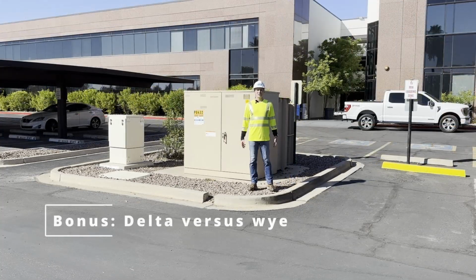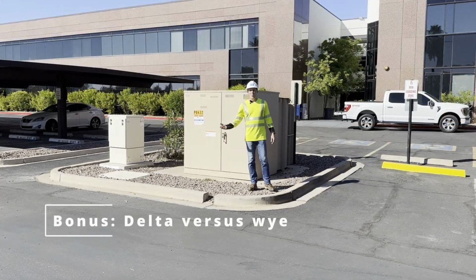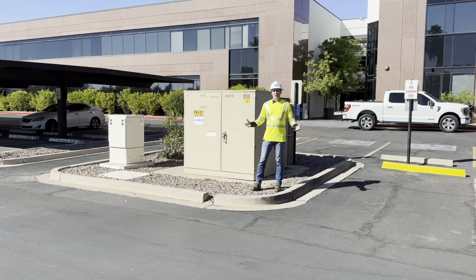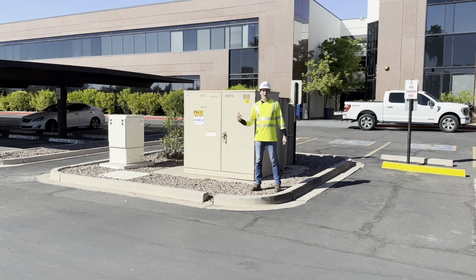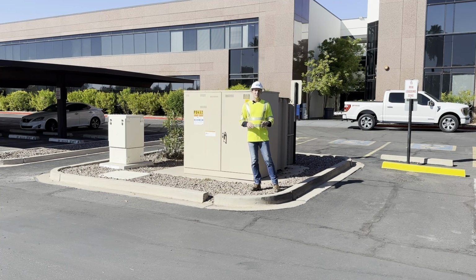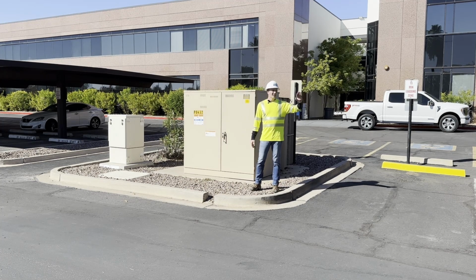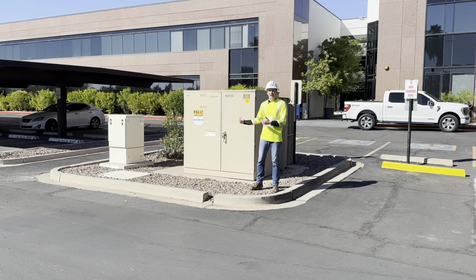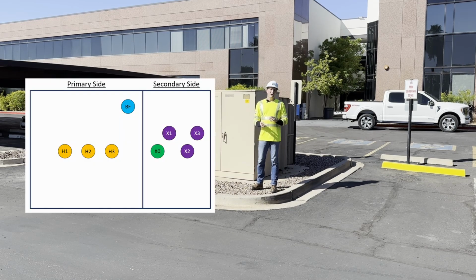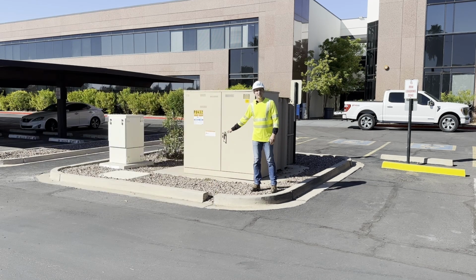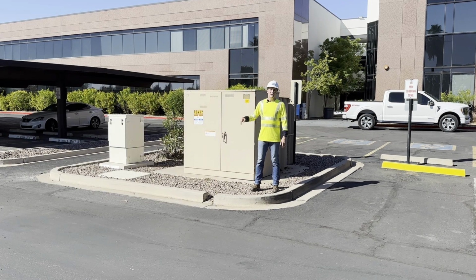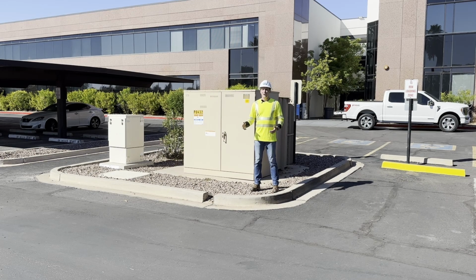Another thing we'll talk about is the difference between delta and Y transformers. For EV charging projects, we actually always need Y service—you can get away with delta sometimes with some electrical trickery, but we'll cover that in a different video. Y service means there's a neutral coming out of the transformer. On the secondary side there are 4 bushings: X0, X1, X2, and X3. X0 is the neutral, bonded to the ground bar in the transformer on the secondary side, and X1, X2, X3 are the three phases going to your project, assuming 3-phase service.